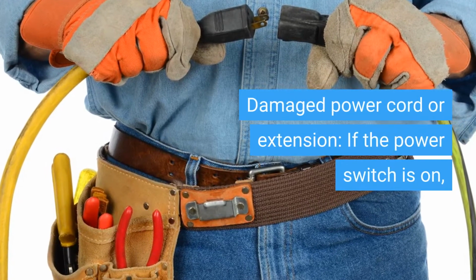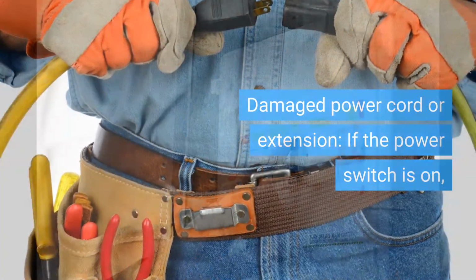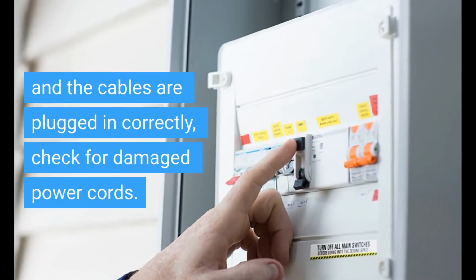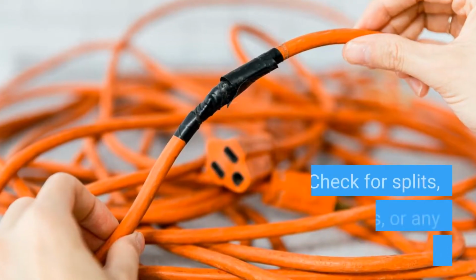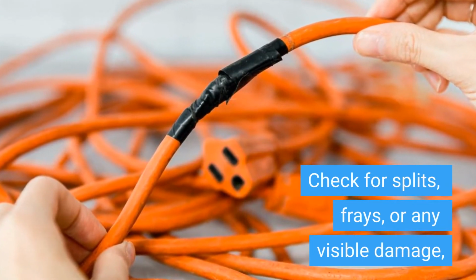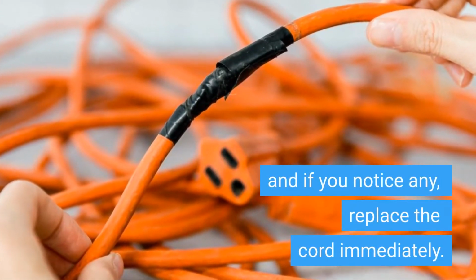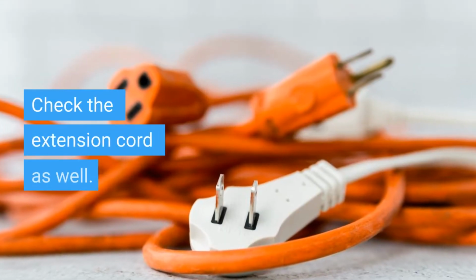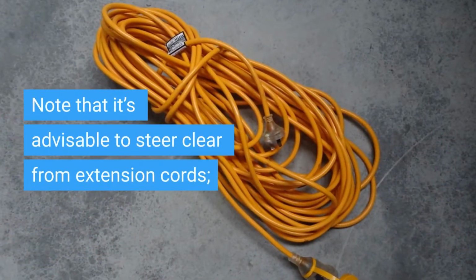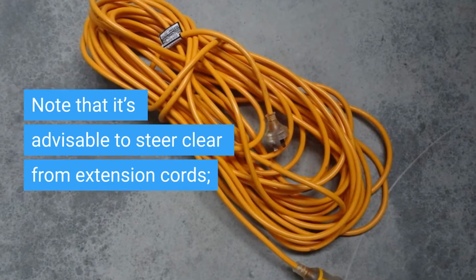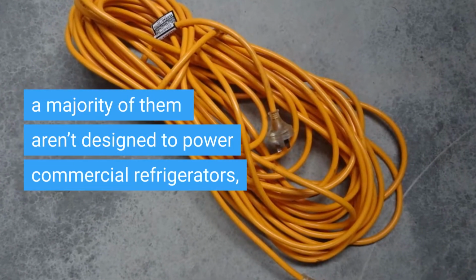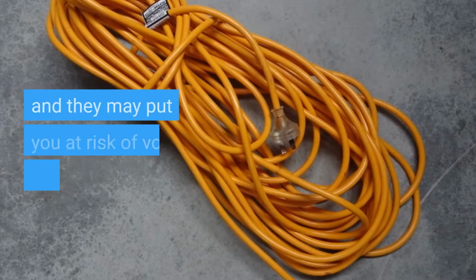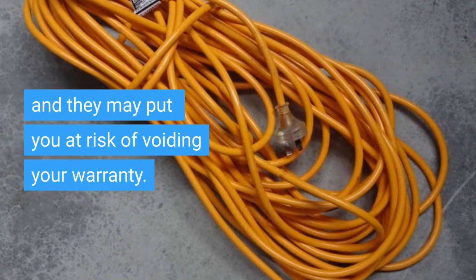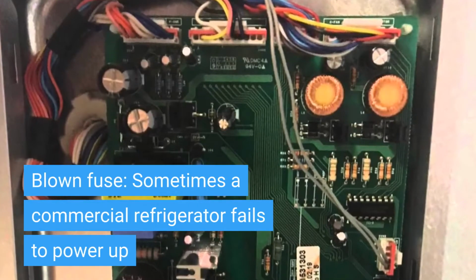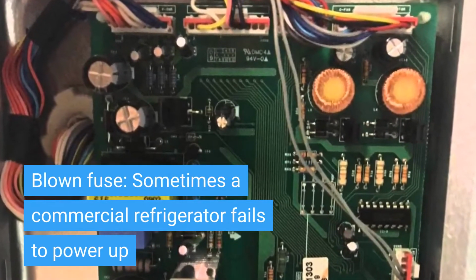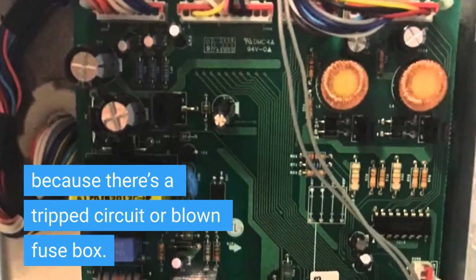Damaged power cord or extension. If the power switch is on, and the cables are plugged in correctly, check for damaged power cords. Check for splits, frays, or any visible damage, and if you notice any, replace the cord immediately. Check the extension cord as well. Note that it's advisable to steer clear of extension cords. A majority of them aren't designed to power commercial refrigerators, and they may put you at risk of voiding your warranty.